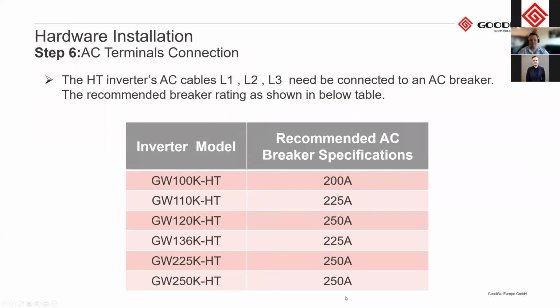So it's important just to note we are using the correct size breakers so that there is no nuisance tripping issues or anything like that. So the 100 kilowatt, we recommend at 200, 110 the 225, 120 the 250. The reason we do recommend larger breakers than the nameplate rating is because of our power boost that we have with all our inverters that's able to output an extra 10%. So the 10% is quite a lot when we come to a 120 kilowatt inverter. So that's why our breakers are quite a bit oversized.